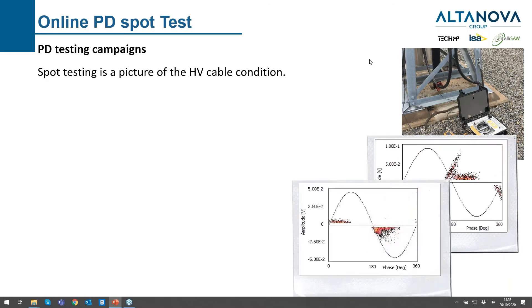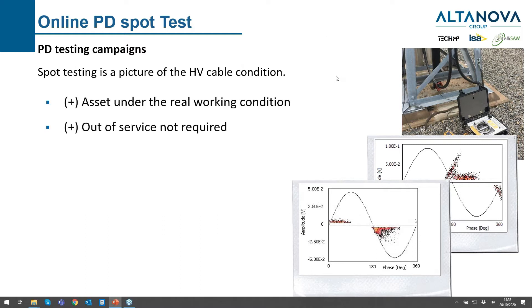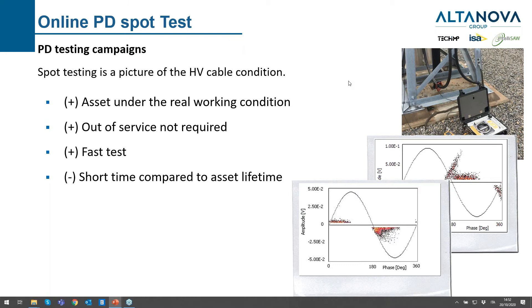We have to consider that spot testing is like a picture of the HV cable condition. There are several good points: the system is working in real working conditions, so we have voltage, current, aging — everything is there. We don't need any out-of-service period. This is a very fast test because we can test three accessories in less than one hour.